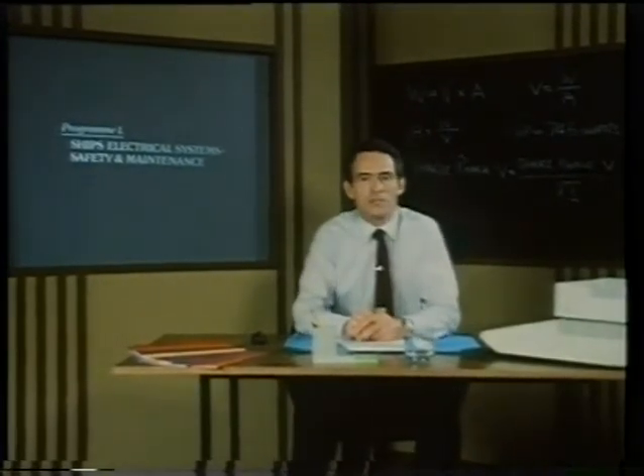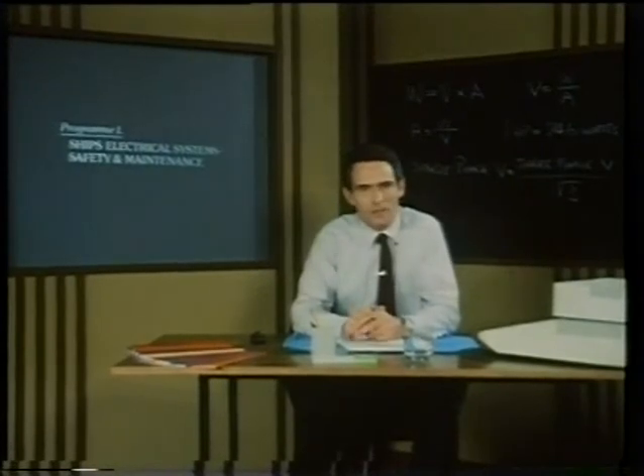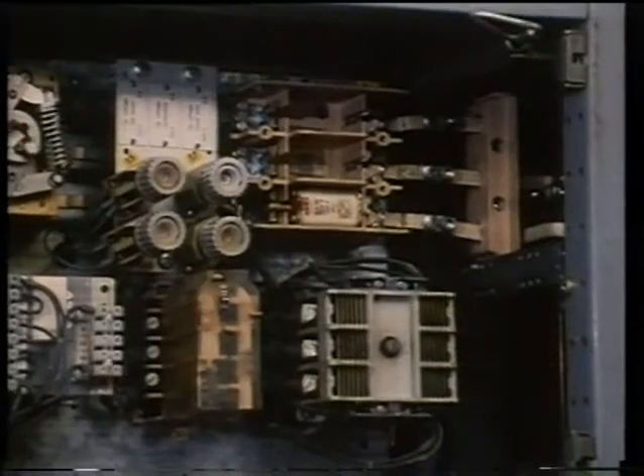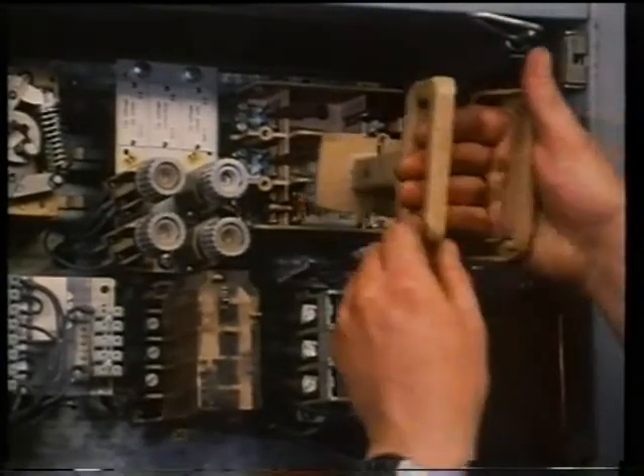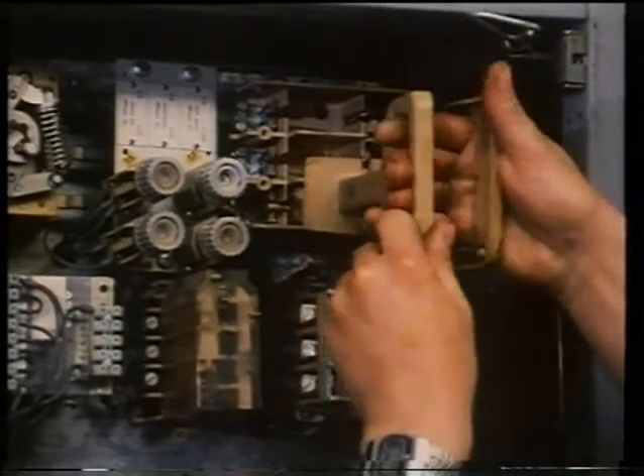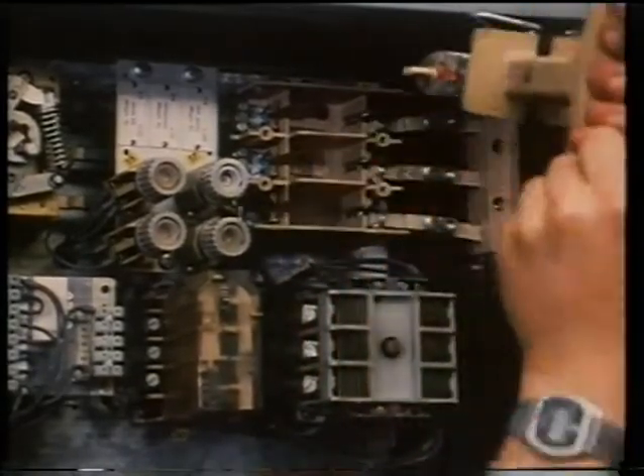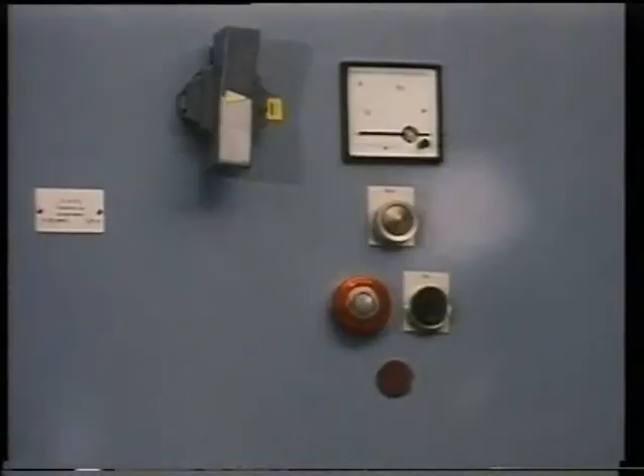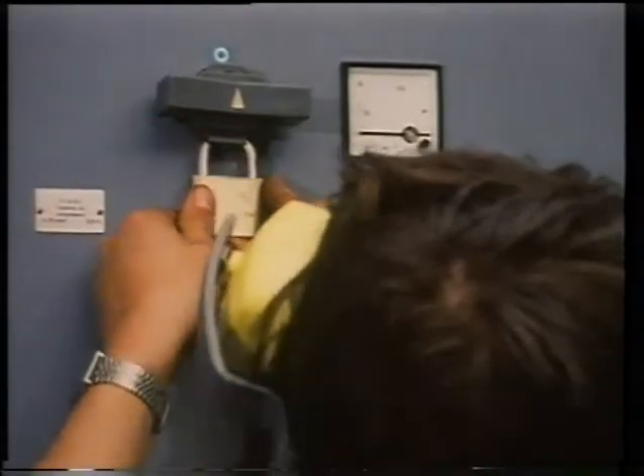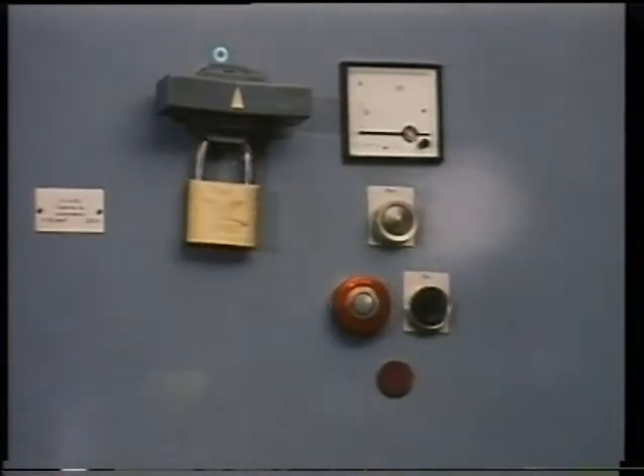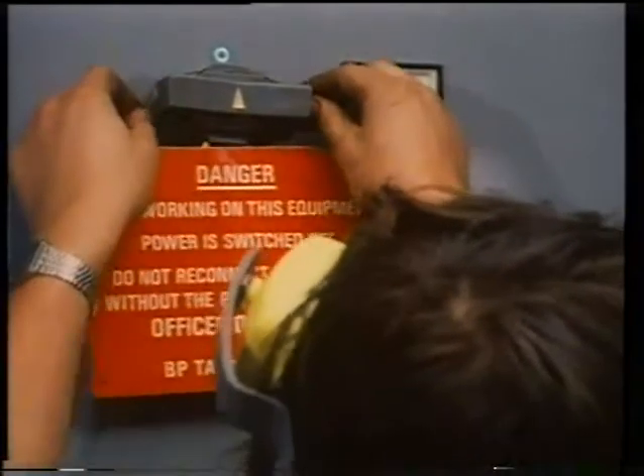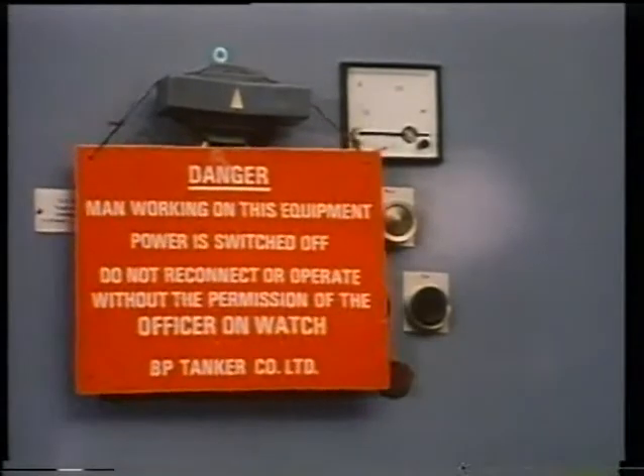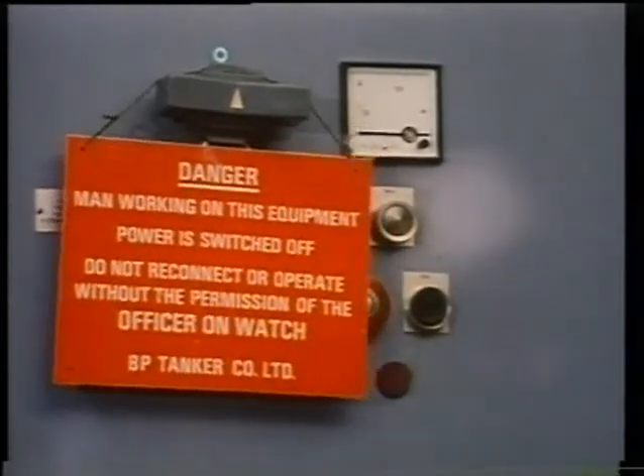Now we must emphasize electrical safety. The golden rule is, before any work is done on an electrical installation, first, isolate the circuit by removing the supply fuses or locking the circuit breaker in the open position so that the circuit cannot be energized accidentally. Then, post a warning sign to alert others that the circuit is being worked on.